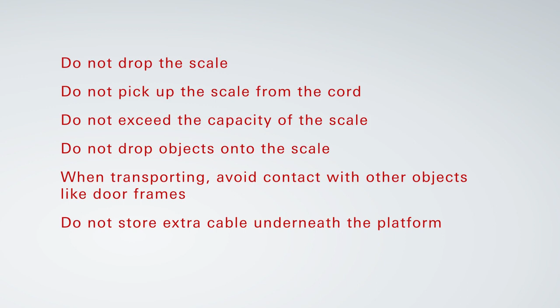We are often asked when preventative maintenance needs to occur. This would start with a periodic examination of the scale's condition. Step on and off the scale several times. The scale should return similar weights. If the weights are off significantly between weighments, move the scale to an open area to be sure the column scales are not touching any other items like curtains in an exam room, for example.